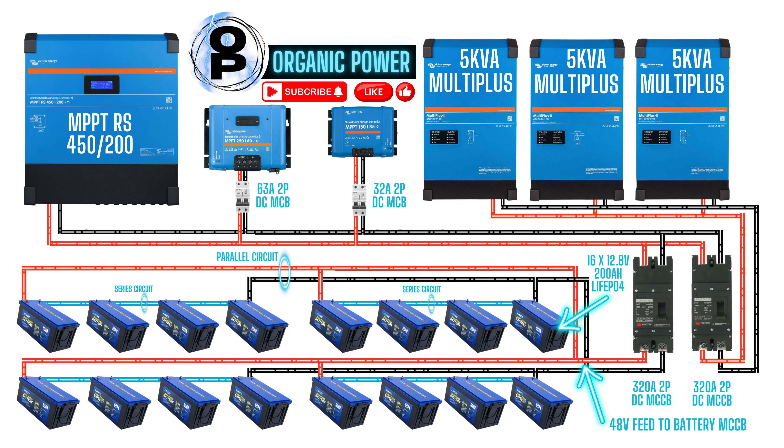The lithium iron phosphate batteries we're using are 200 amp-hours each. The banks of four have four 200 amp-hour batteries. The amp-hours don't multiply when you join a series circuit — only the voltage does. So the voltage goes up to 48 volts, but the amp-hours remain at 200. Over the four banks, we have 800 amp-hours at 48 volts.